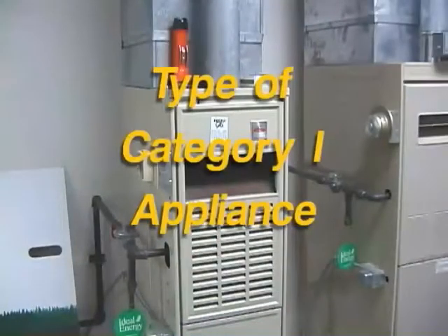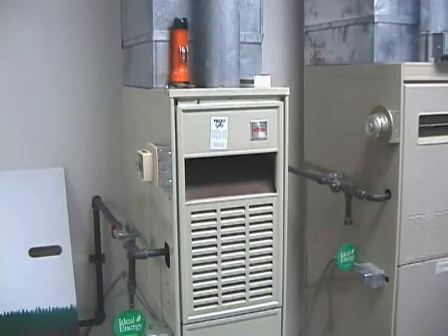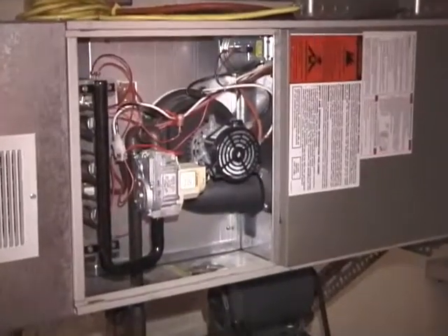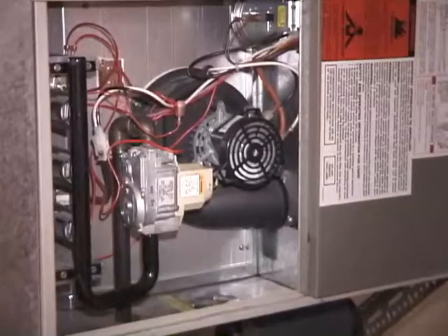Type of Category 1 appliance. Traditional atmospherically vented gas appliances with an open draft hood or dilution port are the most susceptible to draft problems. Oil-fired appliances and mid-efficiency gas furnaces with inducer fans are somewhat less susceptible.